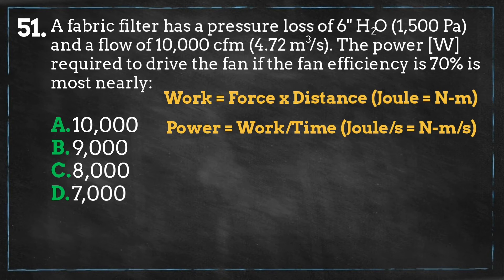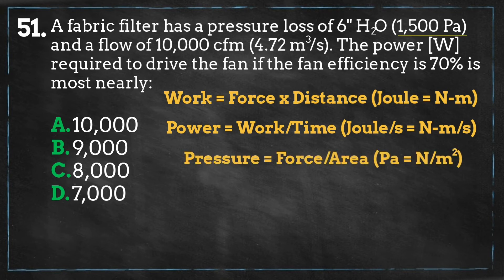We have the pressure drop — the effect of a force applied to a surface — which equals 1,500 pascals. A pascal is defined as the force of one Newton per square meter. We also have the flow rate, which is 10,000 cubic feet per minute or equal to 4.72 cubic meters per second. We can multiply the pressure drop by the flow rate to get units of Newton meter per second, which equals watts.